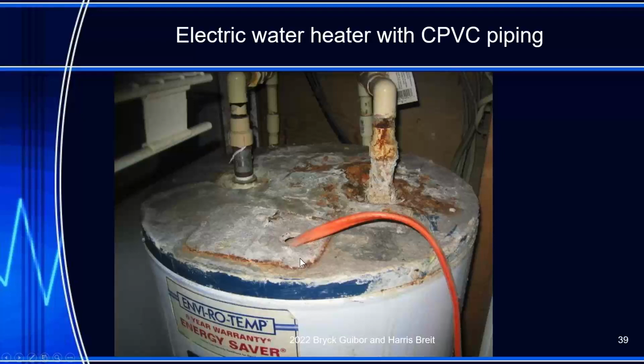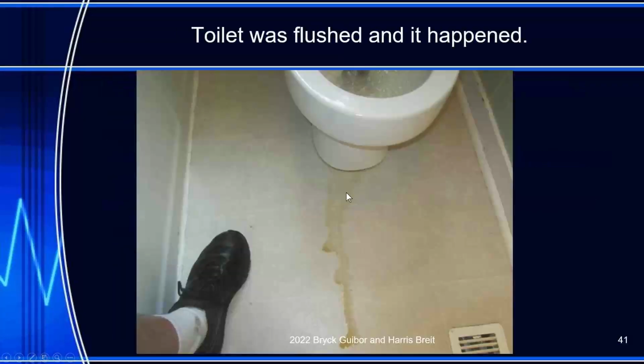Well, we have a piece of Romex, not protected properly, not terminated properly, exposed. Everything is wrong. It's orange in color. What does that tell me? It's a number 10. Okay, so it's colorized. And then back here, I have this leak in this fitting. It's plastic and it's leaking. Could this break apart and leak at any second? It looks like it's been leaking.